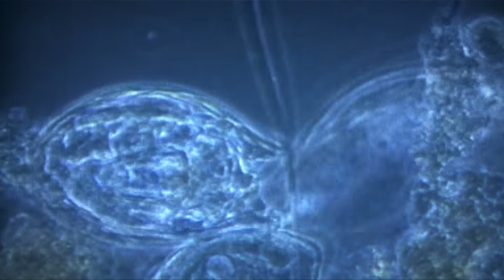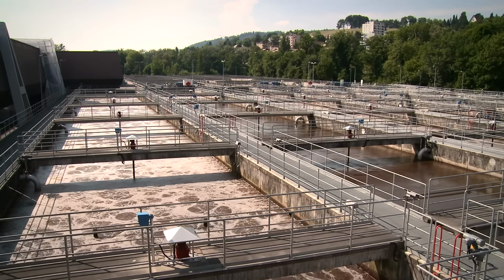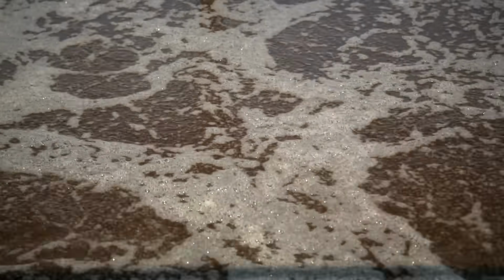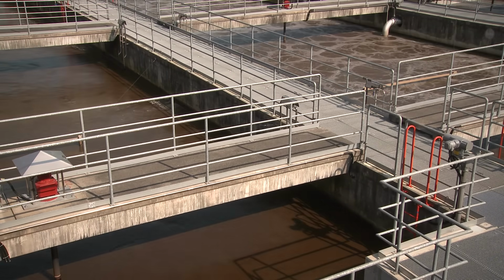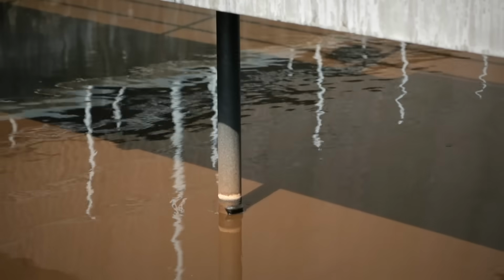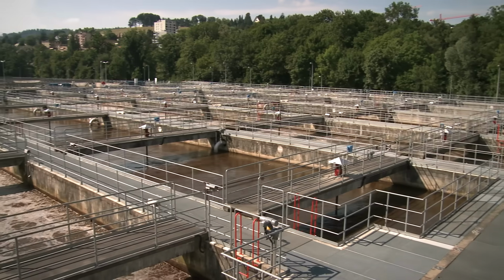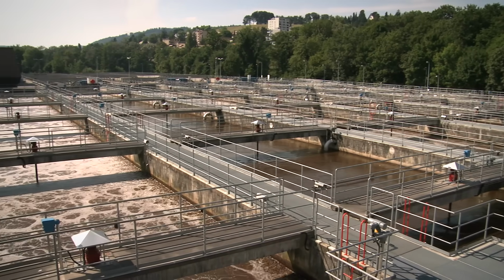While one tank in each lane is fed with water, the other is aerated and mixed. Ammonium is converted to nitrate with oxygen here. The functions of the respective tanks then switch. In the tank that is no longer aerated, without oxygen, the nitrate is converted to elementary nitrogen. By switching the tanks, the plant can flexibly react to different rates of wastewater flows and loads.